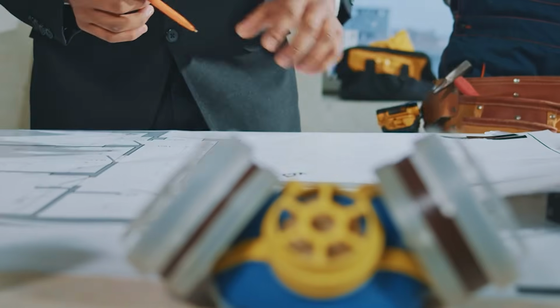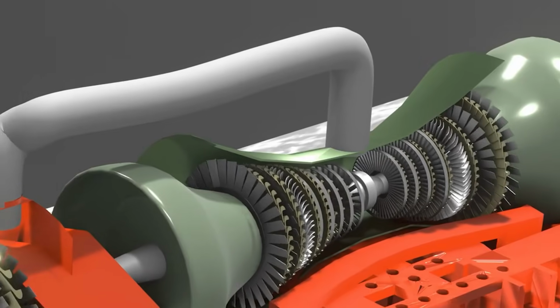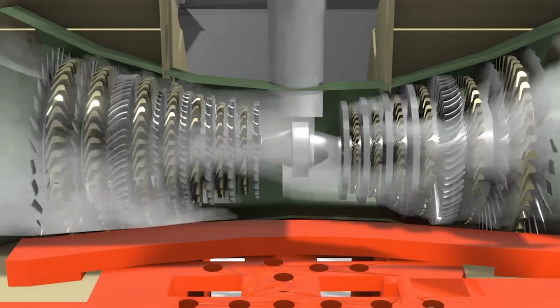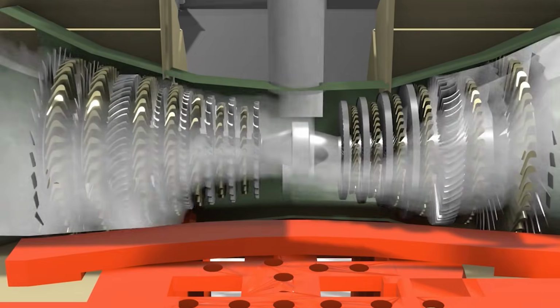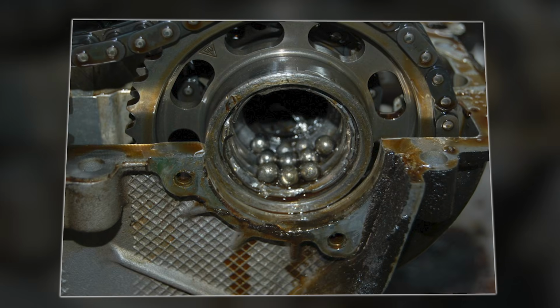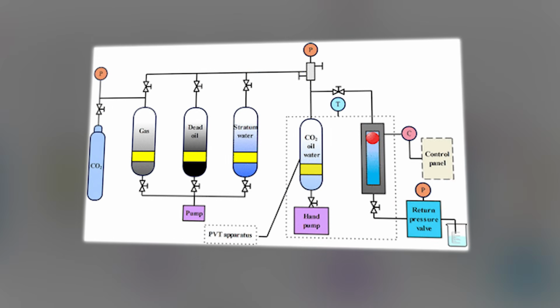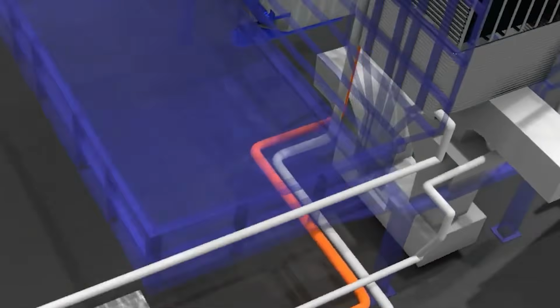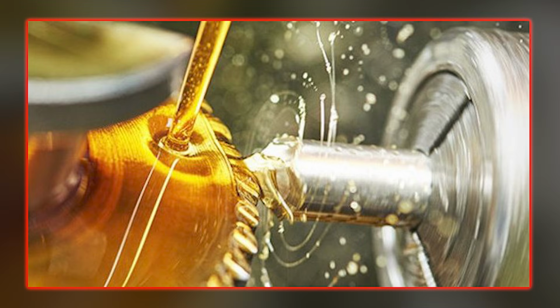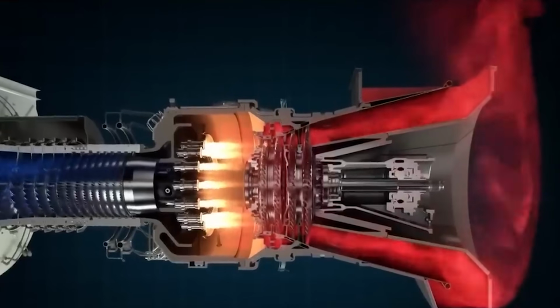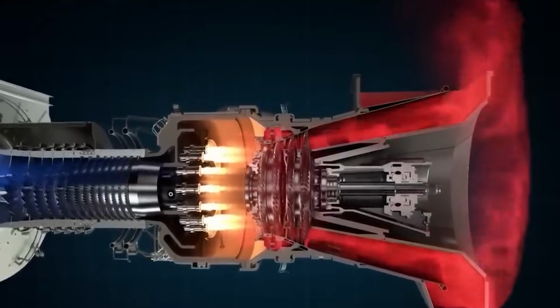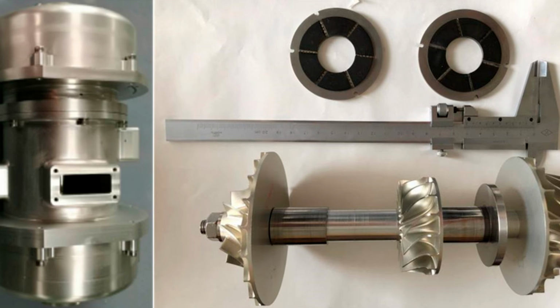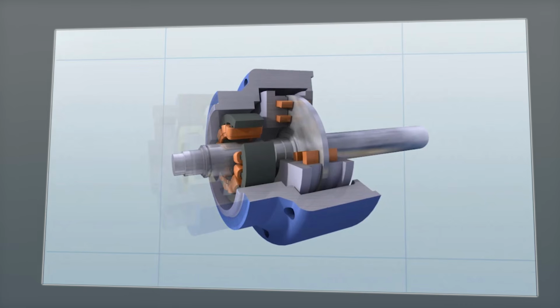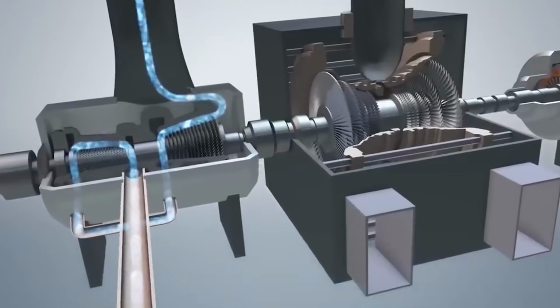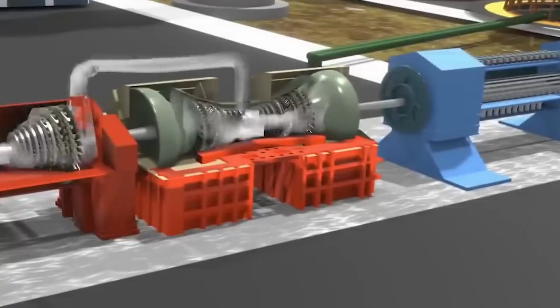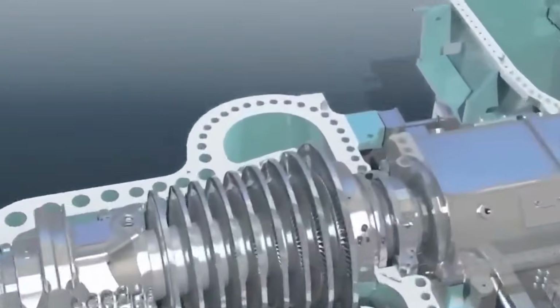And then came the third problem, the one that frustrated engineers perhaps more than any other. The bearings. A supercritical CO2 turbine spins at extraordinary speeds, in some designs north of 50,000 revolutions per minute. At those speeds, conventional oil-lubricated bearings are useless. Not just because of the mechanical stress, but because supercritical CO2 dissolves into lubricating oils, contaminating them and destroying their protective properties. Any oil that leaks into the working fluid contaminates the entire closed-loop system, so you cannot use oil, which means you need bearings that function without any physical lubrication at all. The solutions that eventually emerged: gas foil bearings that ride on a thin cushion of CO2 itself, and magnetic bearings that suspend the rotor shaft in mid-air using electromagnetic fields with no physical contact whatsoever, are each an entire engineering discipline unto themselves. Each one took decades to develop to the point of reliability.